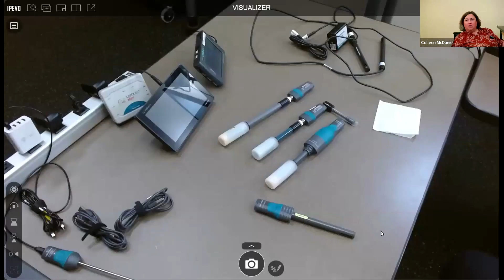The Go Direct conductivity probe doesn't have any ranges you have to set, it operates at full range. But the LabQuest sensor has a small switch box on the side where you have to decide which range to measure conductivity in. Most people, I tell them to start in the mid-range, 0 to 2000 microsiemens, and if the water is below 200, go to the next range down, which is 0 to 200. So that's how the range changes the conductivity reading on a LabQuest sensor.